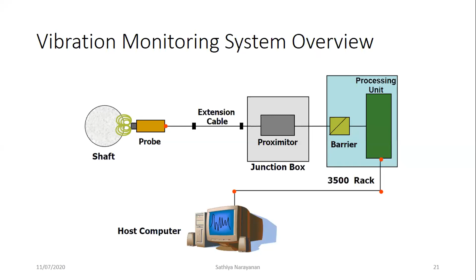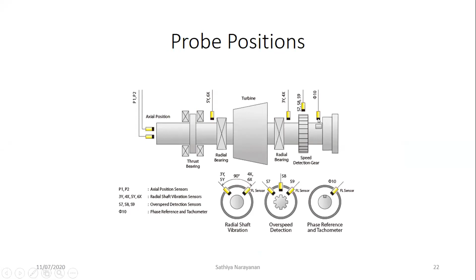Now, in this slide, you are seeing the various probe positions where you can place the sensors. So what are the types of sensors we can use? We have the position sensors. The position sensors are about the alignment of the shaft being proper, which is why we have the axial position sensor. Then we have radial shaft vibration sensors, which measure the vibration produced by the shaft. And then we have overspeed detection sensors at S7, S8, and S9, which measure the speed of the gear. If the speed of the gear goes over a particular limit, then we have to trip this particular equipment. And then we have phase reference. Phase reference is nothing but it checks the misalignment.